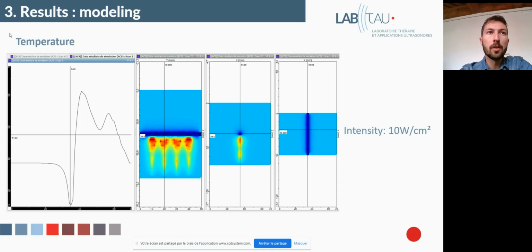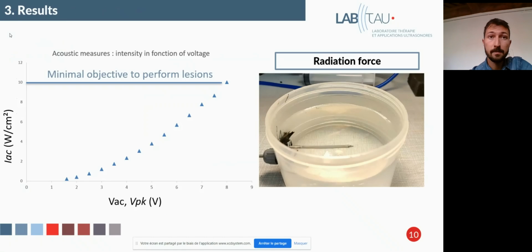For the modeling, here we have a map of temperature with 4 lobes, and we have this kind of lesions for a treatment of 10 minutes with an intensity of 10 watts per square centimeter. So the goal for us was to reach 10 watts per square centimeter in intensity with our probe, because the modeling shows that it's something that can allow us to perform lesions. Here is an acoustic measure of the intensity, and we see that we reach this objective of 10 watts per square centimeter. It was kind of hard to achieve this because of the cooling system, which is very, very hard to put in place because of the dimension of the probe.